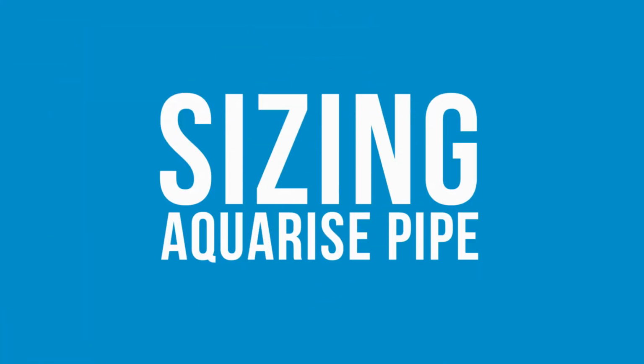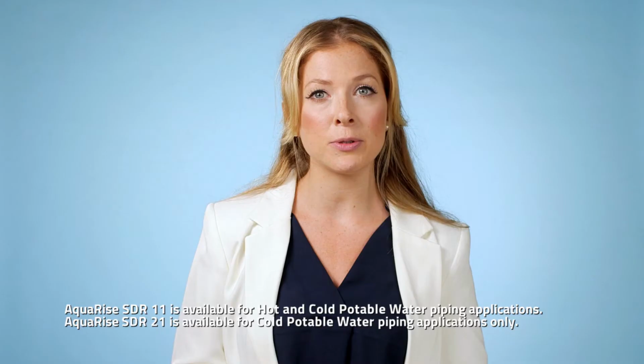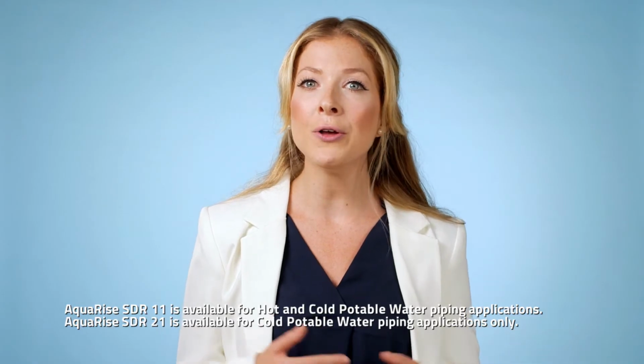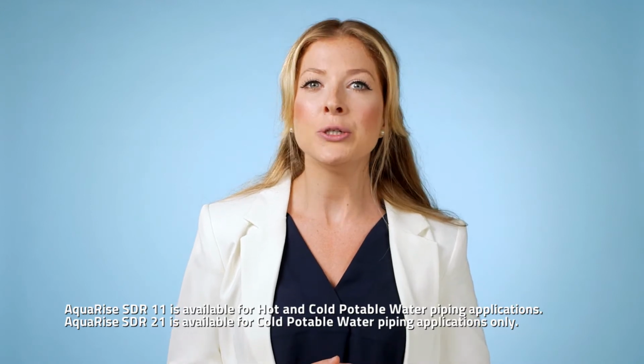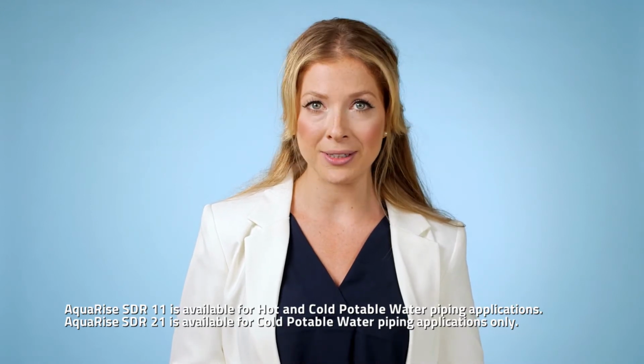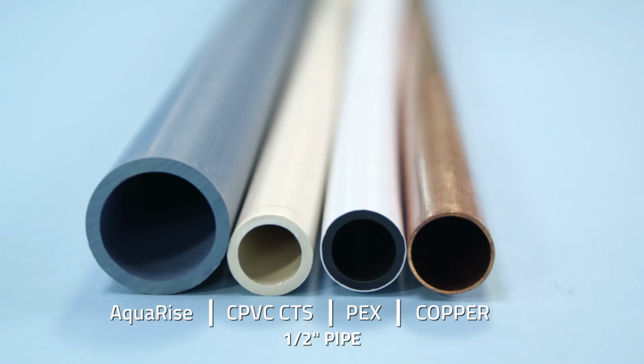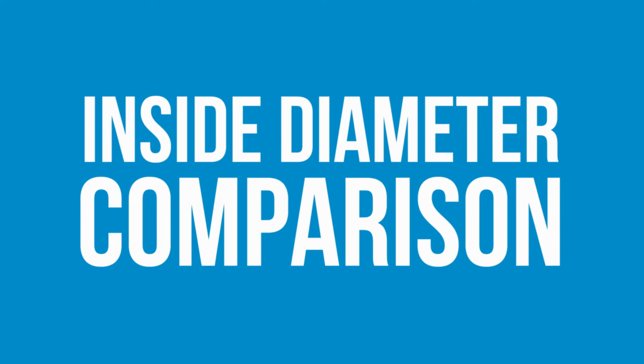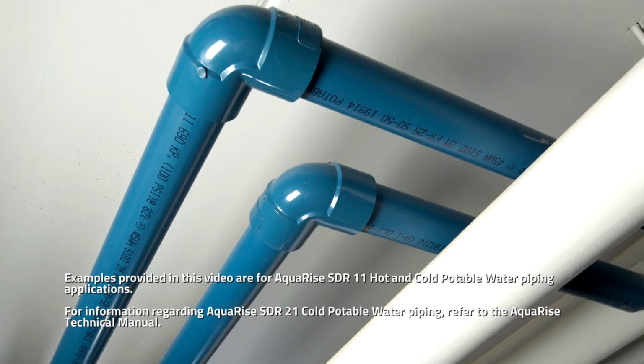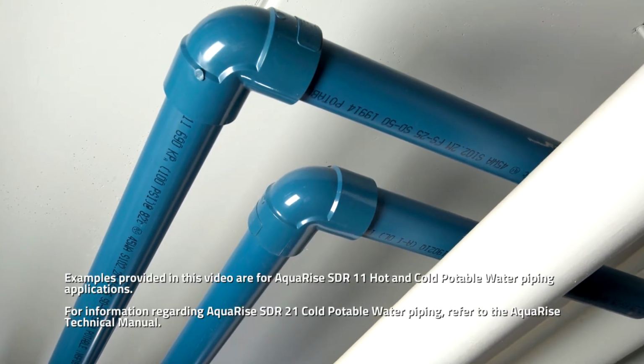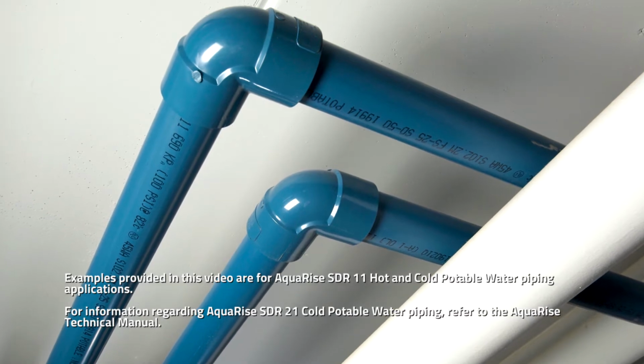Proper sizing design is necessary to create a balance between flow velocity, flow volume, and pressure head losses. Due to similar inside diameter dimensions, AquaRise may use design sizes similar to copper. Depending on design velocity considerations, AquaRise may even permit designers to use one nominal size smaller than copper. An AquaRise water distribution system offers increased flow capacity when compared to alternative piping materials.